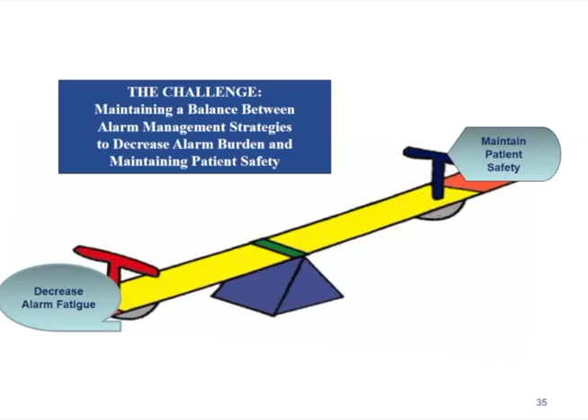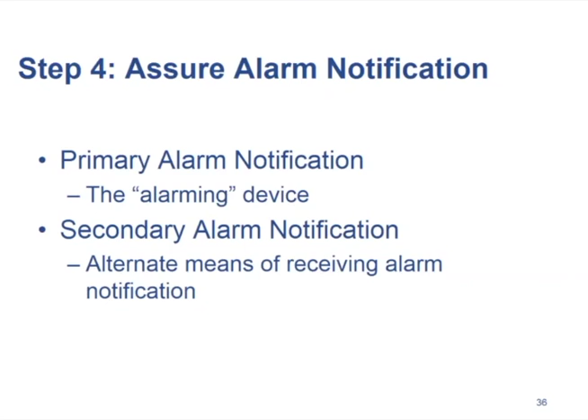With any plan, though, it's a balance between alarm management strategies that decrease noise and alarm burden and maintaining patient safety. Units have to be comfortable with the plan that you put in place. Step 4 is to assure that you have an alarm management notification system in place. Now, obviously, the alarms will be heard at the primary medical device if someone's standing right next to that device. But what if no one is near the device? How will staff be notified? This is known as secondary alarm notification. It's the backup plan or the alternate means of receiving alarm notification.